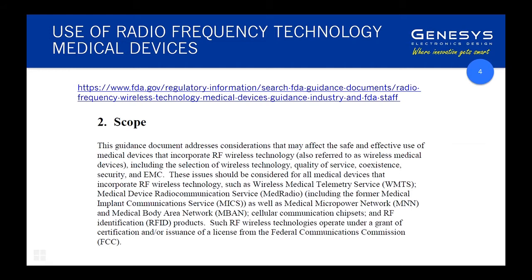There's a particular FDA document addressing this — the URL is referenced on the slide — and it's particularly helpful in analyzing the pros, cons, and constraints of using different radio technologies in different environments. From my point of view, I'm very comfortable using Bluetooth and Wi-Fi in the majority of care environments. I start to get concerned in an intensive care ward with lots of electronic equipment, and even more so in an operating theatre, particularly if a patient is connected to conductive catheters. I'd be extremely concerned if someone tried to use 4G or 5G cell phone connectivity in an operating theatre — that's asking for trouble.